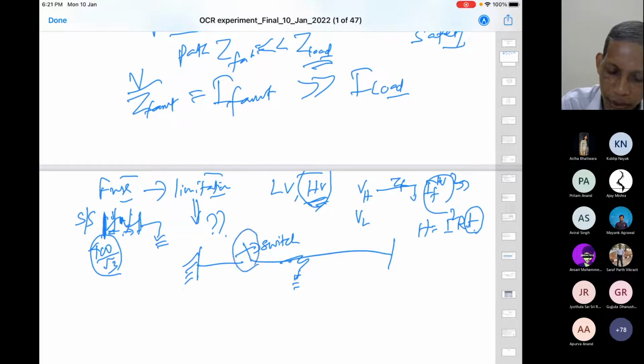So we require a mechanical switch because a fuse has limitations. This mechanical switch cannot make a judgment on whether it is a fault situation or not. A fuse works in its own way: the pin gets melted because of I squared R t heating.